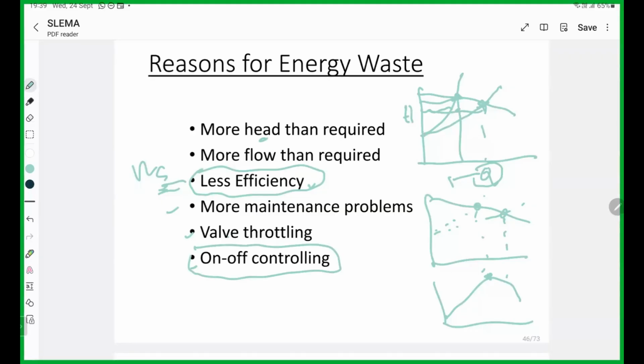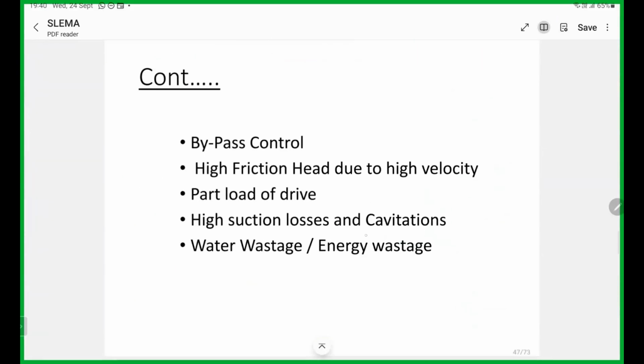You have to keep in mind that continuous pumping is always the most efficient system. On-off controlling is not efficient. The reason is that the system curve is here, and continuous pumping is somewhere here. But if you go for on-off controlling, then definitely the flow rate is higher and the head is higher, right? So keep in mind that continuous pumping is the best option for energy conservation. For controlling, we have bypass control and valve throttling. Some sort of controlling is there, but in terms of energy conservation, our suggestion is continuous pumping.